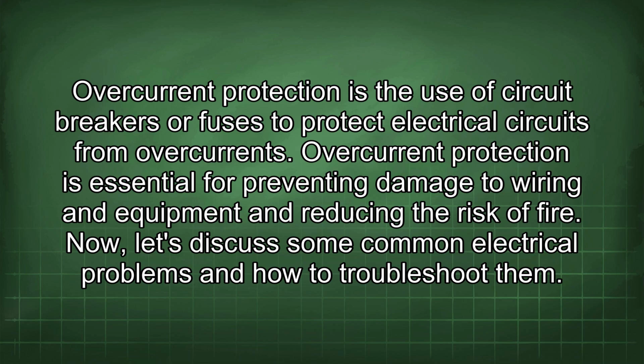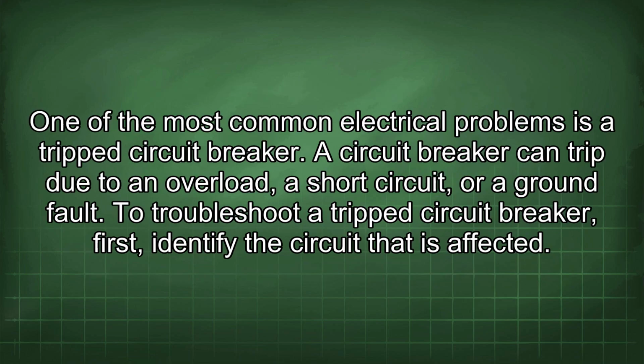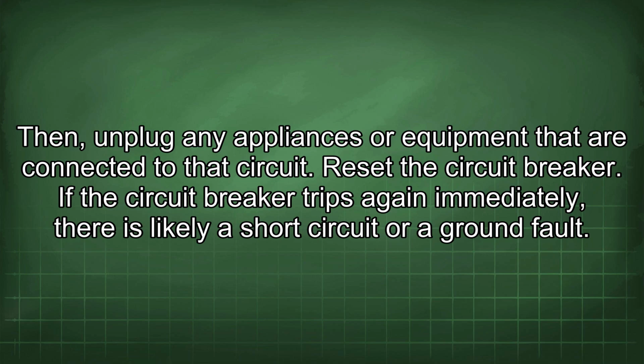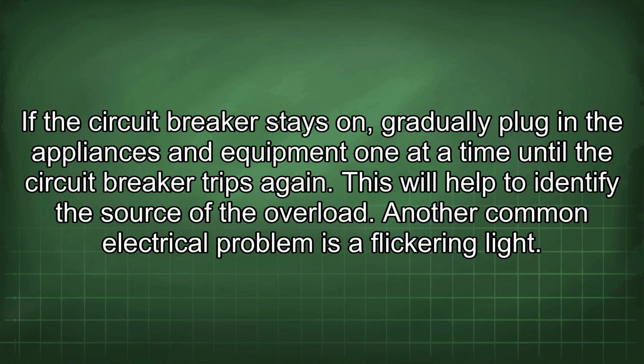Now let's discuss some common electrical problems and how to troubleshoot them. One of the most common electrical problems is a tripped circuit breaker. A circuit breaker can trip due to an overload, a short circuit, or a ground fault. To troubleshoot a tripped circuit breaker, first identify the circuit that is affected. Then unplug any appliances or equipment that are connected to that circuit. Reset the circuit breaker. If the circuit breaker trips again immediately, there is likely a short circuit or a ground fault. If the circuit breaker stays on, gradually plug in the appliances and equipment one at a time until the circuit breaker trips again. This will help to identify the source of the overload.